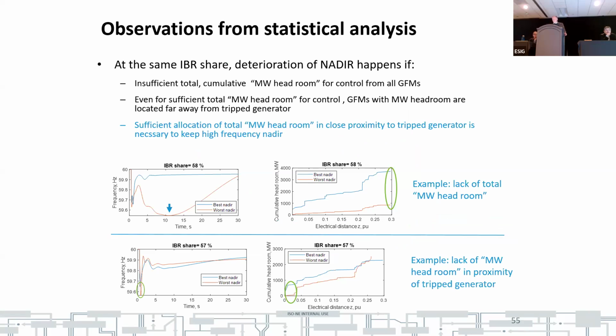And this slide shows two typical patterns for that statistical run. On the top graph, an illustration for a situation when deterioration of nadir is caused by low total megawatt headroom for control, as shown over there. So these are two cases with approximately the same penetration of IBR, like 58% over there, but very different total headroom for control. And lack of headroom for control results in significant reduction of nadir.